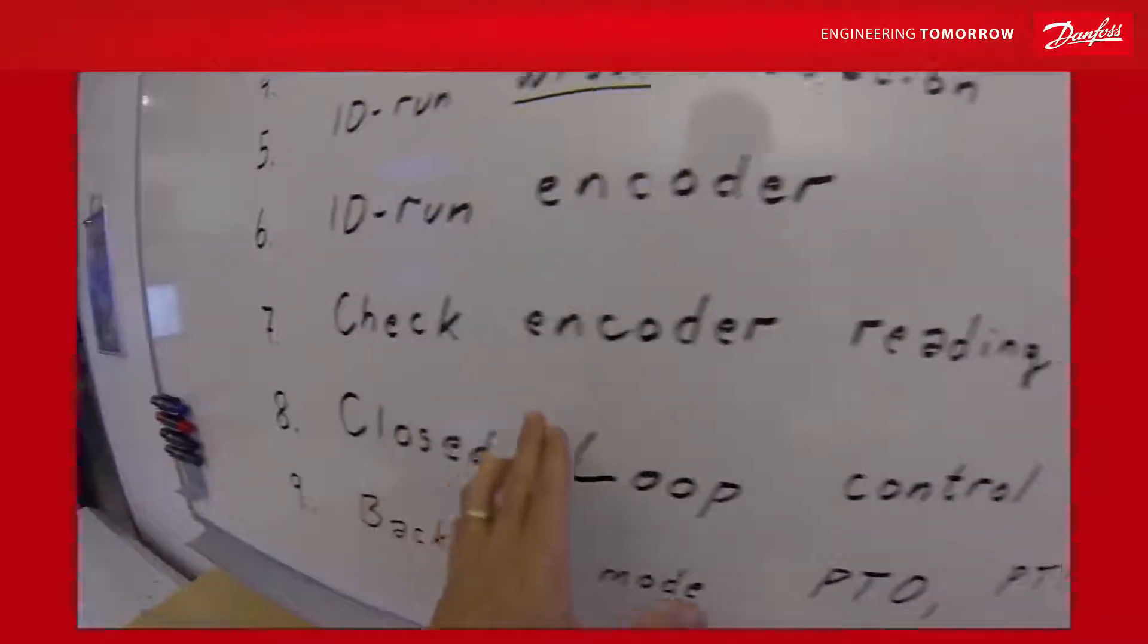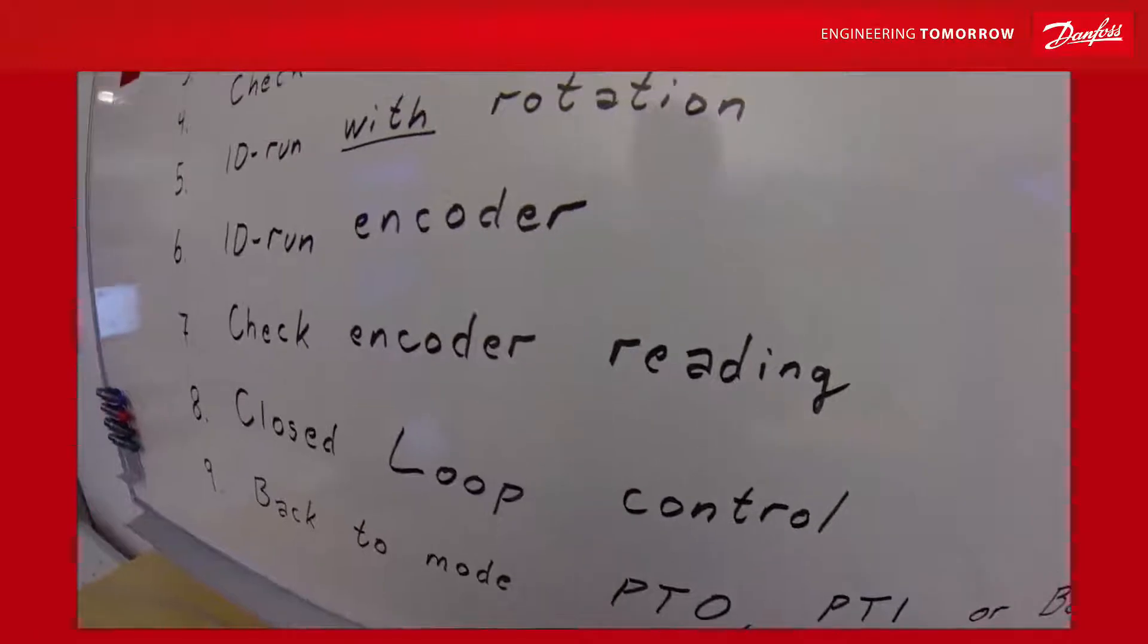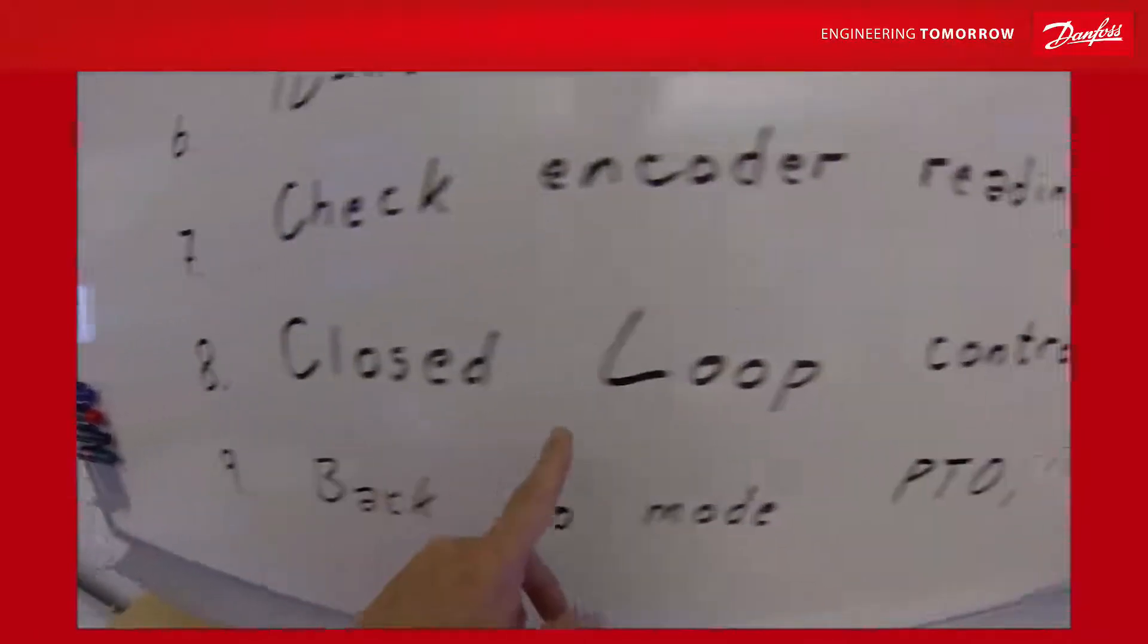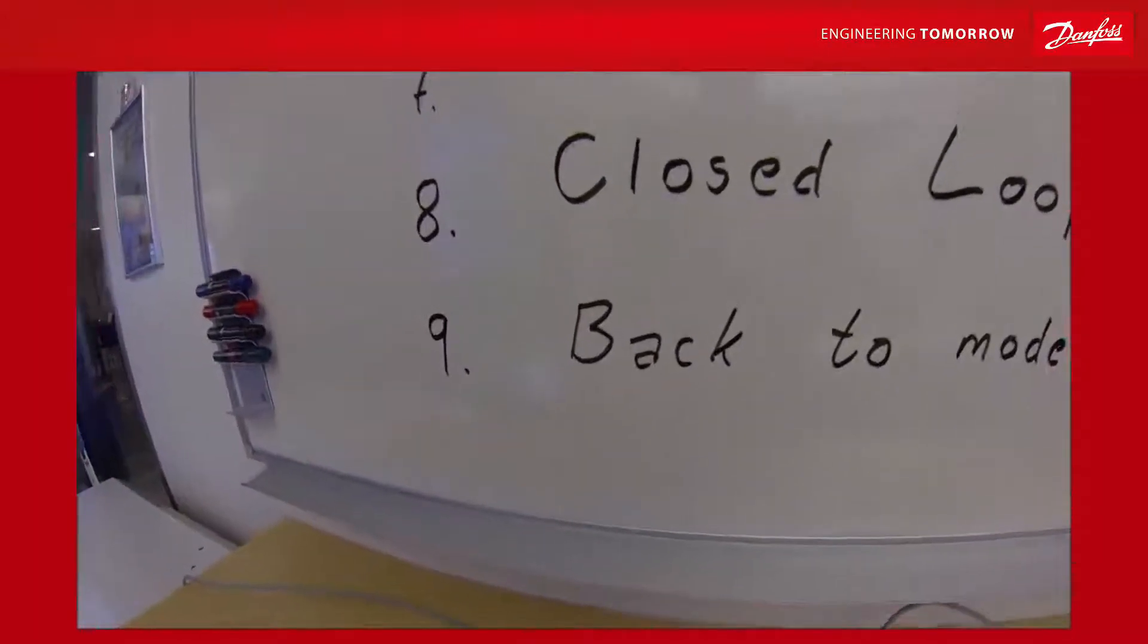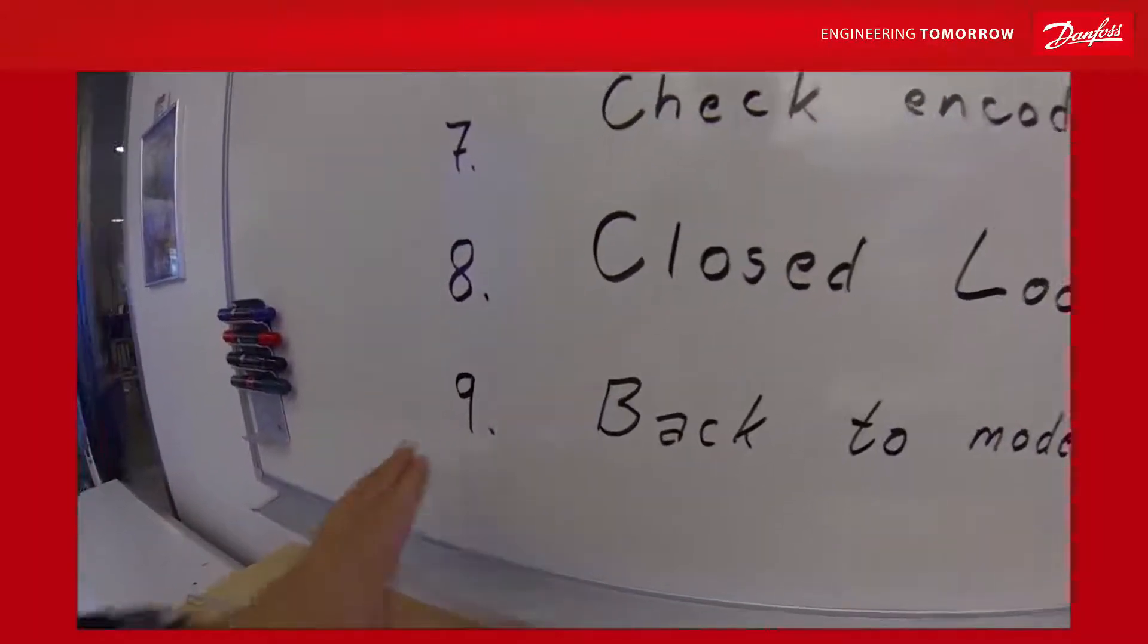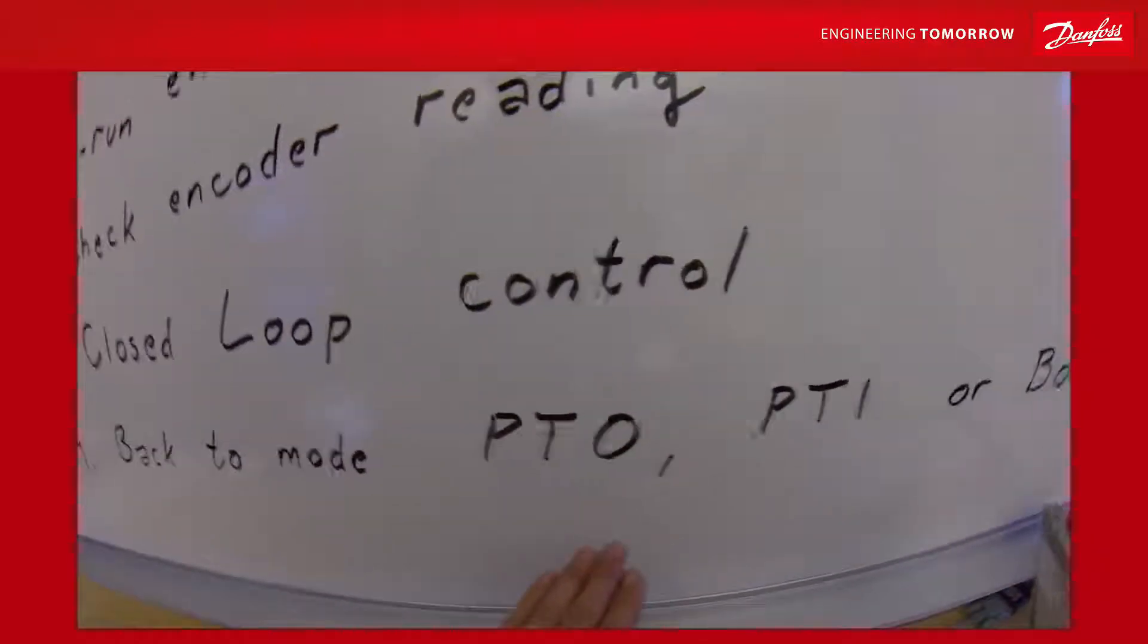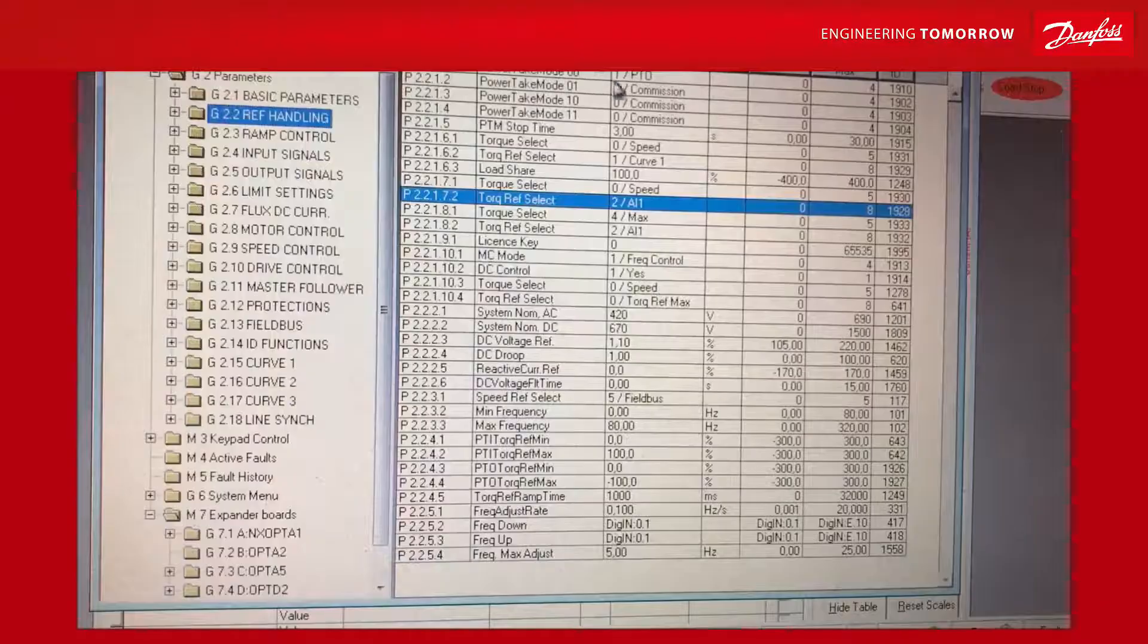We do the identification of the encoder and check that the encoder reading, direction, and scaling are correct. Then we can turn the drive to closed loop mode and check that we are running nicely in closed loop before we switch the mode back to power take-out, power take-in, or boost mode.